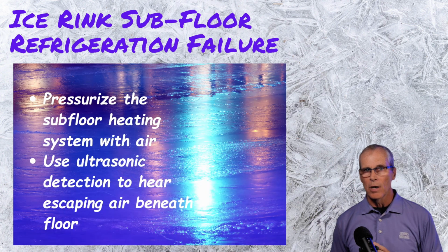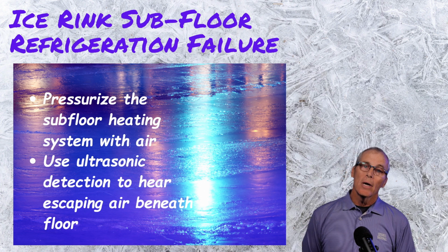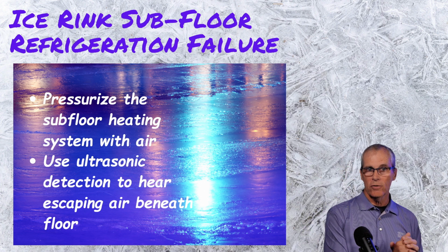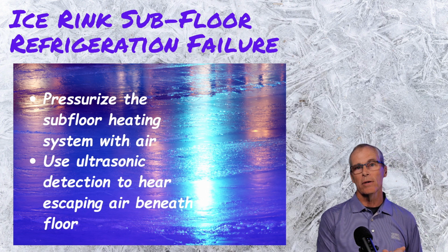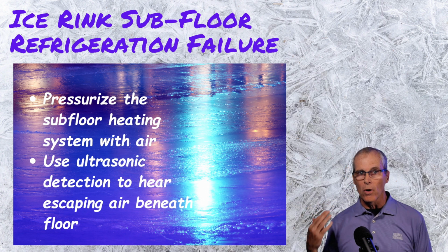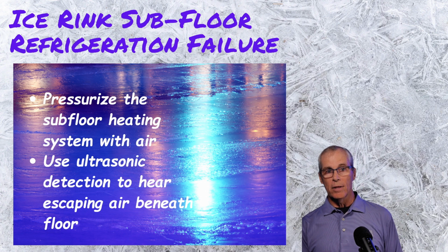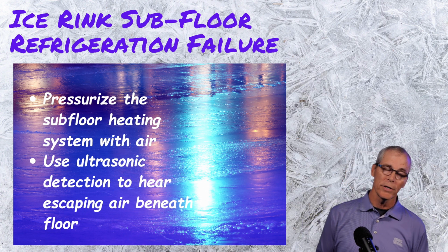Well, we brought in a special team that had air. They'd use air compressors to pressurize that HVAC system, or that heating system that was warming the ground, and listen for air leaks underground with ultrasonic detection equipment. And that's what they did. And they found one spot where the signal was very clear.